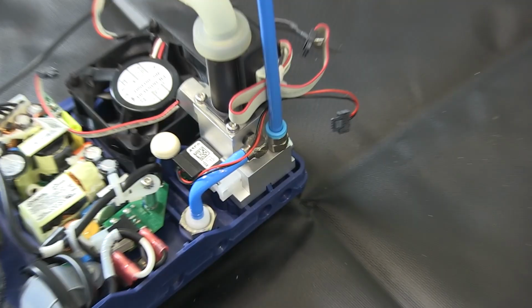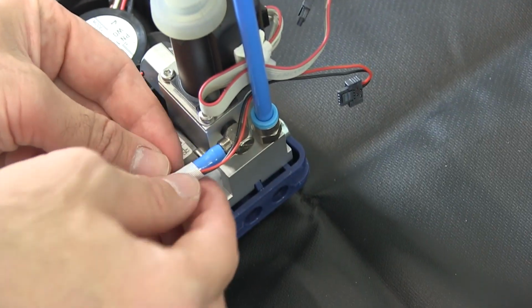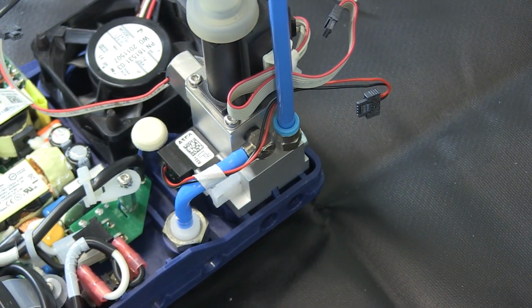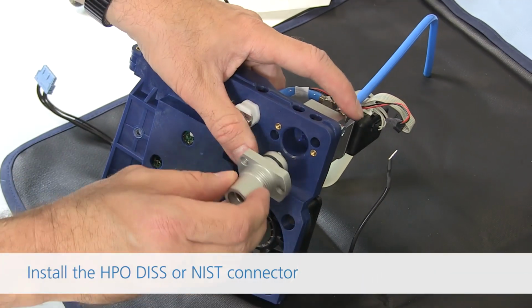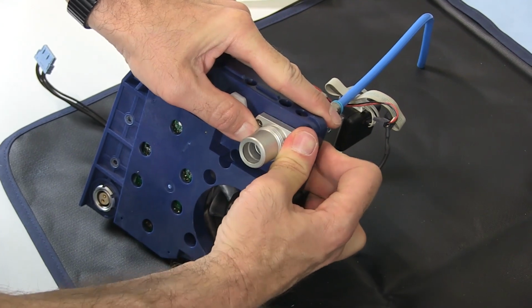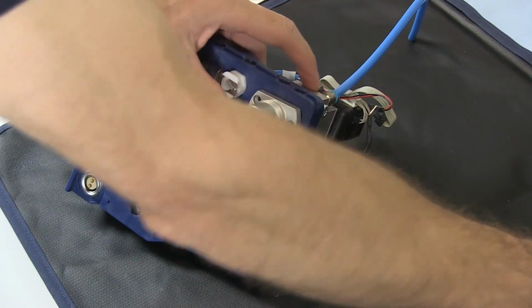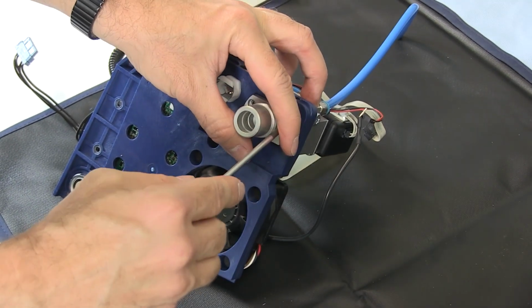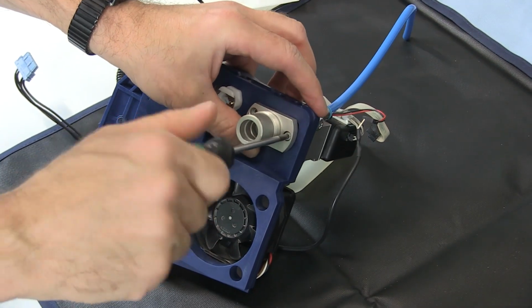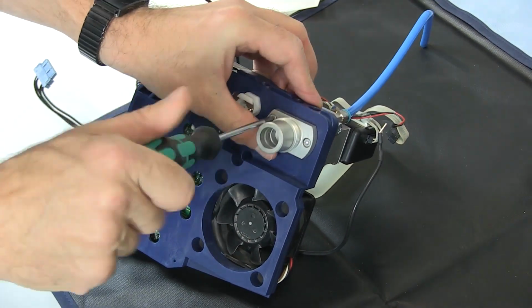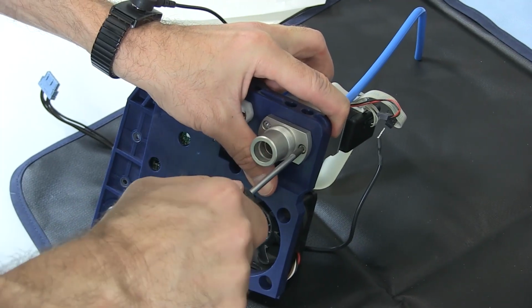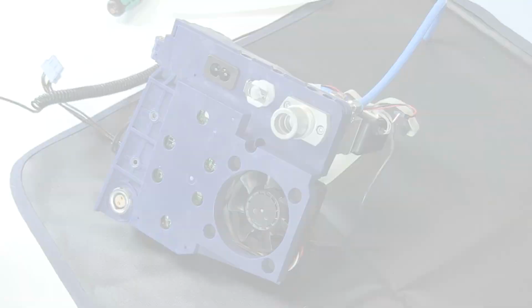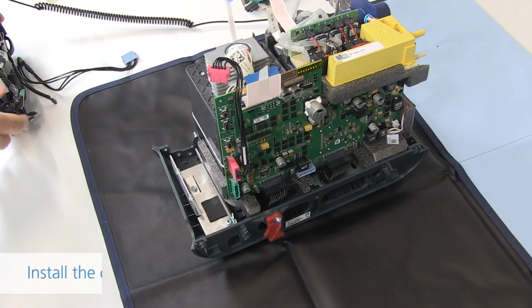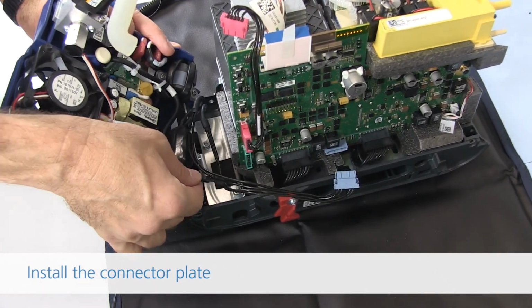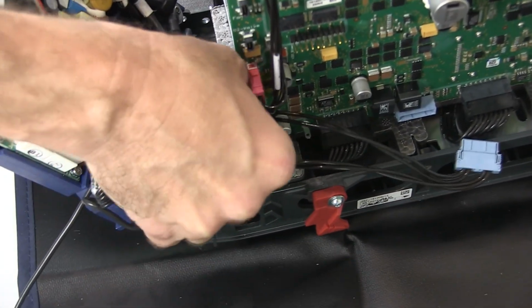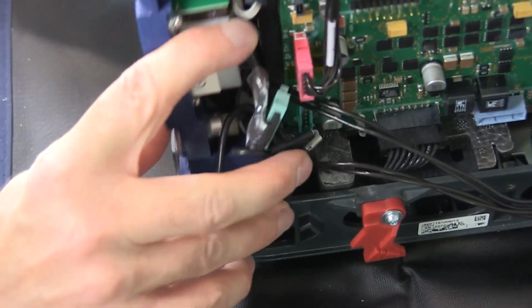Attach a strip of the carbon fibre tape around the LPO tube and nebulizer valve cable. Install the HPO DISS or NIST connector, then install the 2 screws on the DISS or NIST connector and tighten them. Position the connector plate on the bottom cover. Connect the 2 ground terminal cables from the AC power input cable and the protection board to the terminal lugs on the mounting plate.